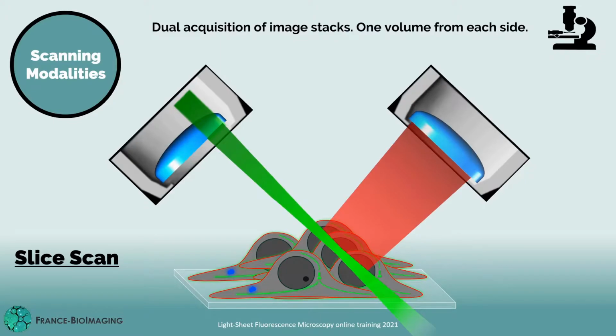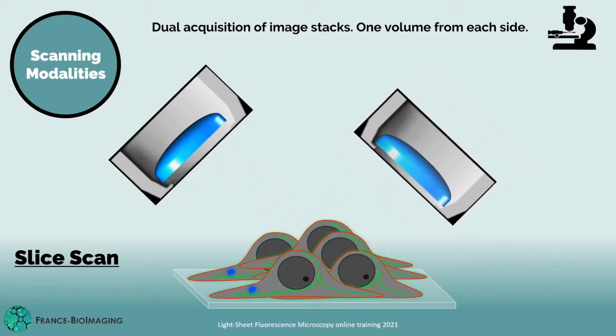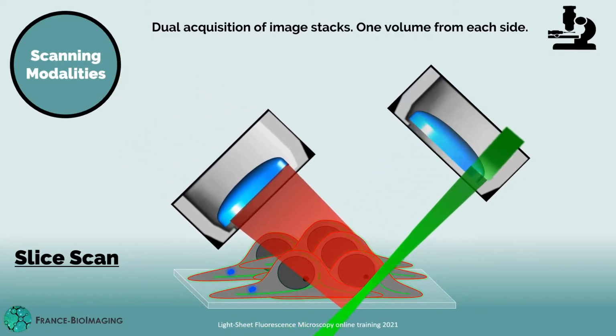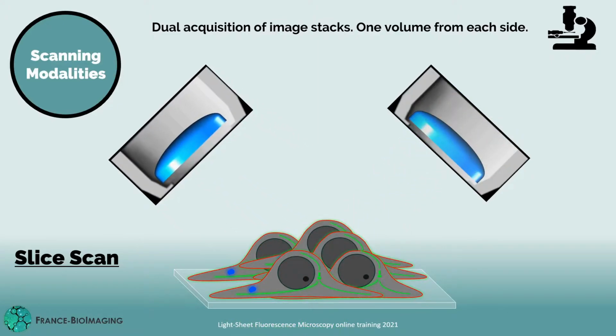Once the whole volume has been acquired on one side of the sample, each arm can switch from illumination to detection and vice versa, acquiring the same volume from a different angle. We'll call path A the view where the beam illumination comes from the left-hand side and detection is done on the right-hand side, and path B the one where the illumination comes from the right-hand side and detection is done on the left-hand side. The volume that can be acquired in this fashion is limited by the light penetration depth, the range of the piezo stage, as well as the field of view of the objective. In our case, that corresponds to 150 by 330 by 330 microns for a 40x objective using the full camera sensor size.